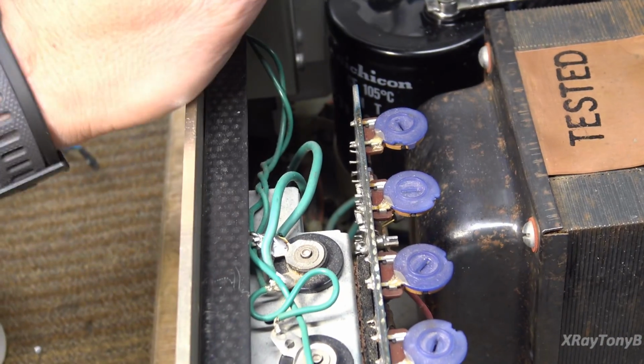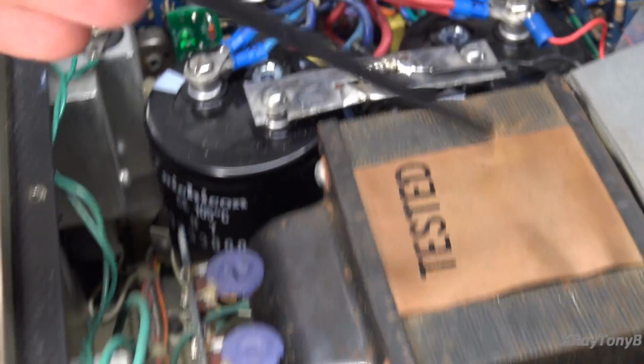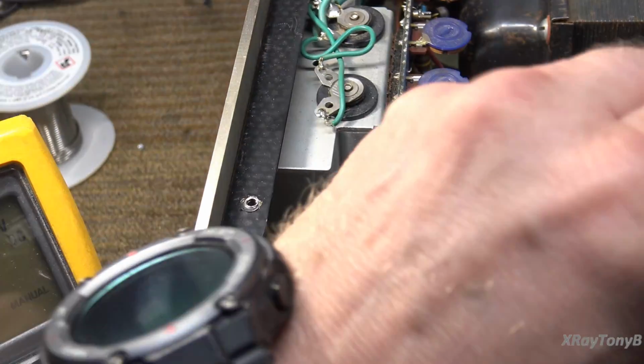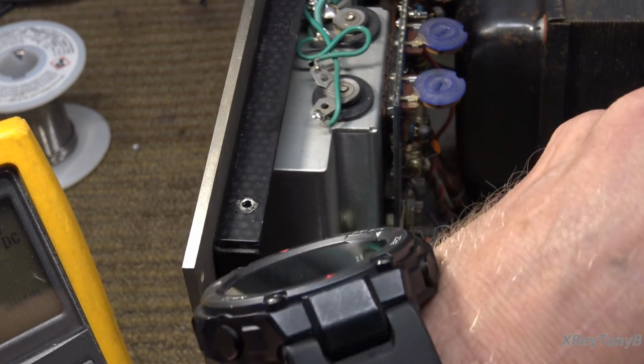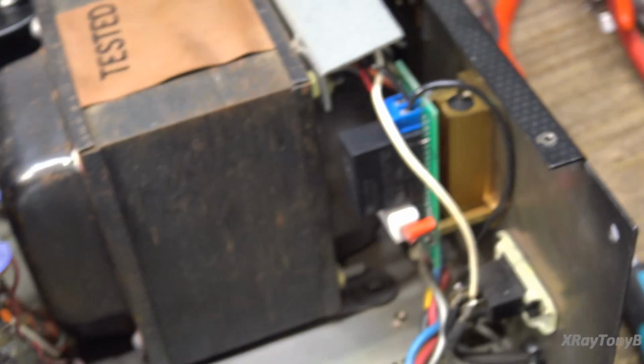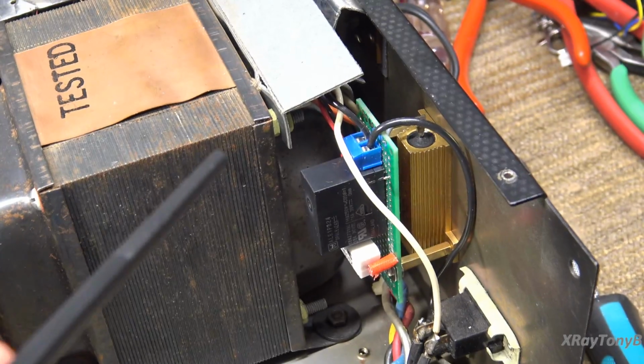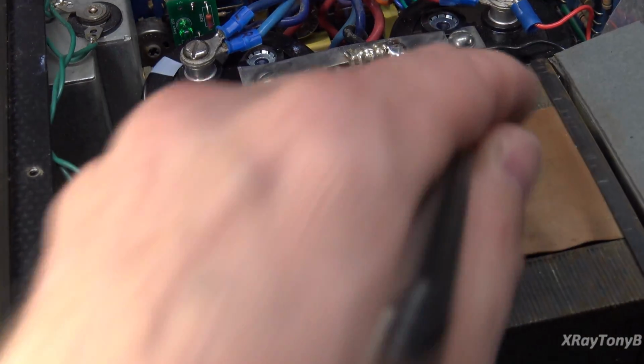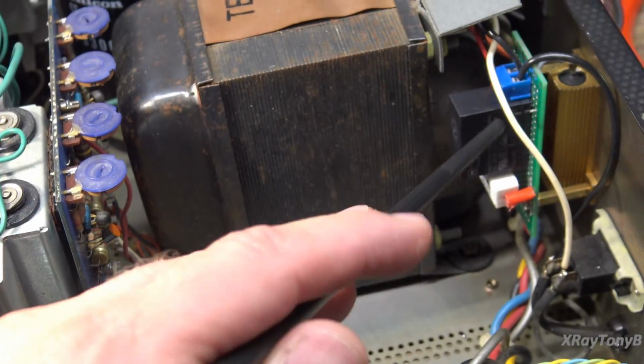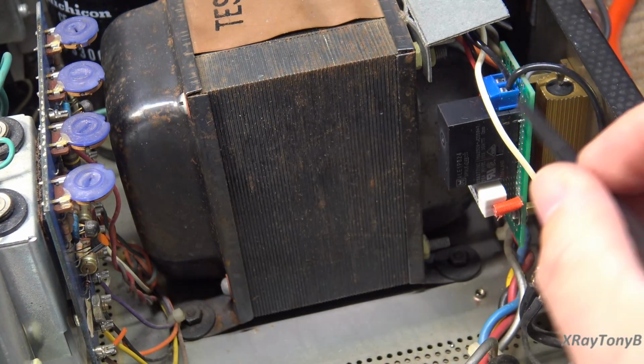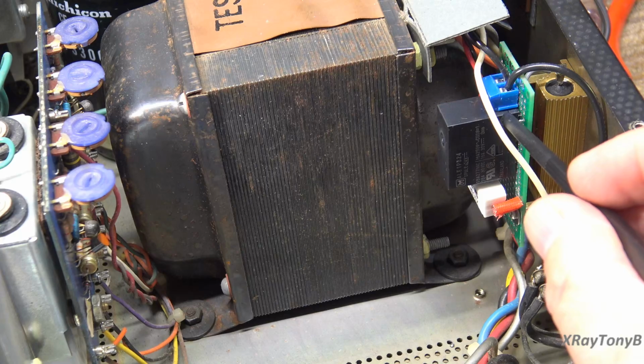So the capacitors will draw really heavy current from the transformer. The transformer will then, on the primary side, draw heavy current through the resistor. Now, that's how it's supposed to work. Once this capacitor begins to charge, it has to get up to a certain level before the voltage across this relay will get high enough to pull it in.